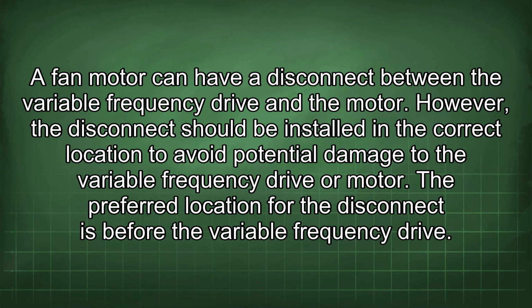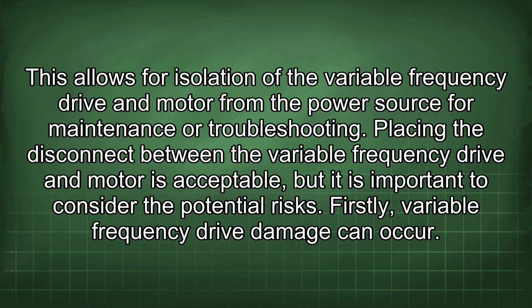A fan motor can have a disconnect between the variable frequency drive and the motor. However, the disconnect should be installed in the correct location to avoid potential damage to the variable frequency drive or motor. The preferred location for the disconnect is before the variable frequency drive. This allows for isolation of the variable frequency drive and motor from the power source for maintenance or troubleshooting.